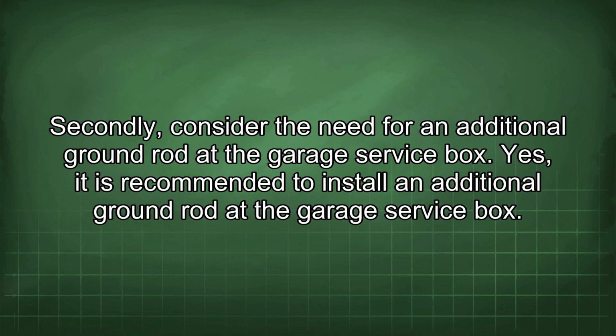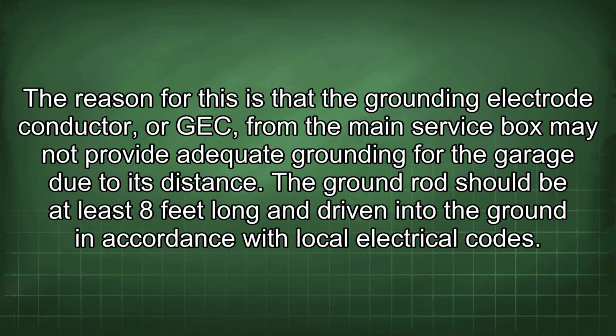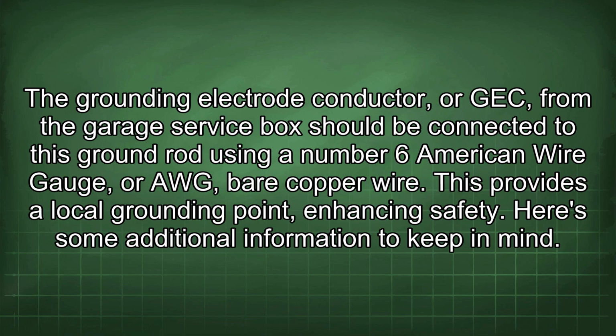Secondly, consider the need for an additional ground rod at the garage service box. Yes, it is recommended to install an additional ground rod at the garage service box. The reason for this is that the grounding electrode conductor, or GEC, from the main service box may not provide adequate grounding for the garage due to its distance. The ground rod should be at least 8 feet long and driven into the ground in accordance with local electrical codes. The GEC from the garage service box should be connected to this ground rod using a number 6 American wire gauge, or AWG, bare copper wire. This provides a local grounding point, enhancing safety.